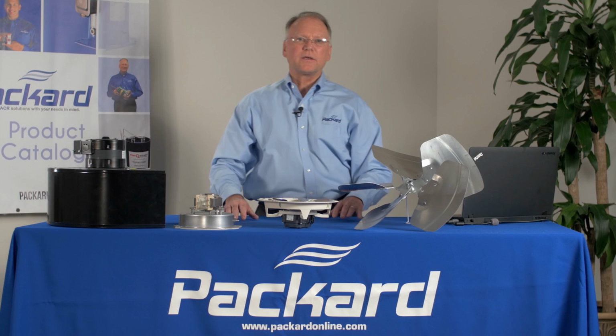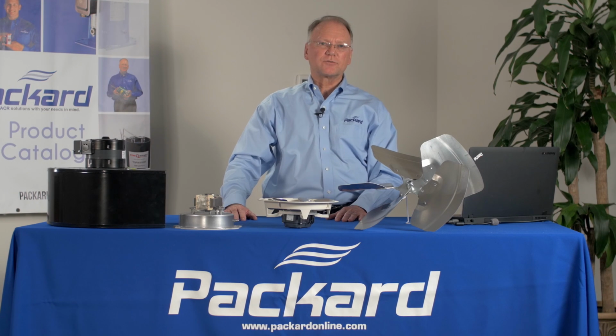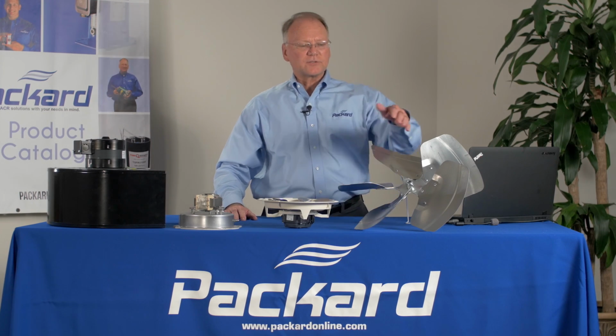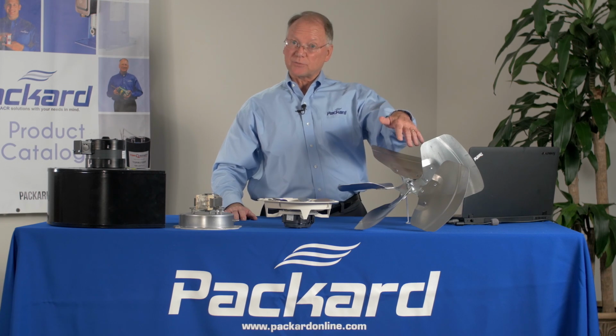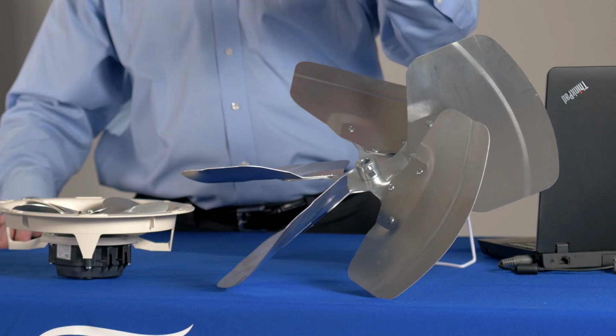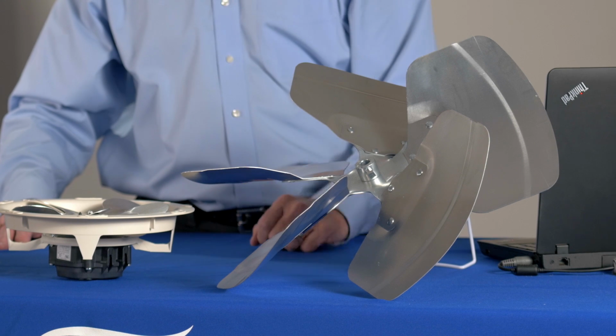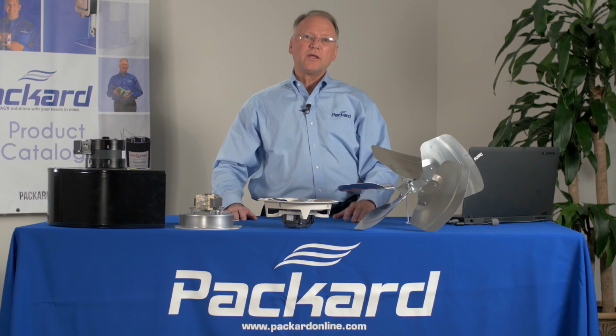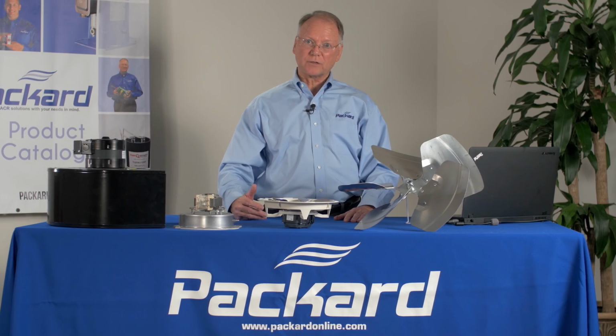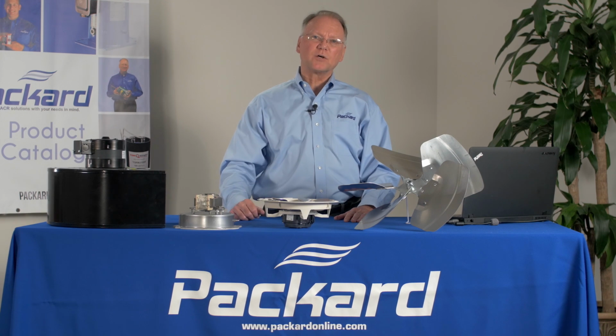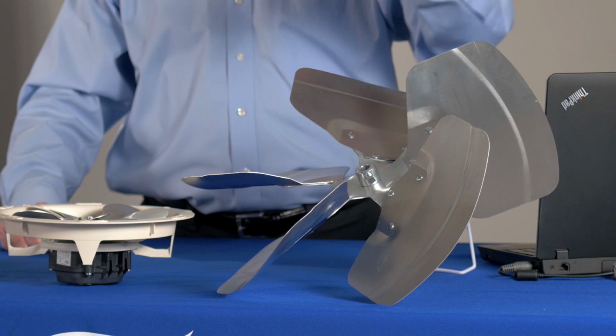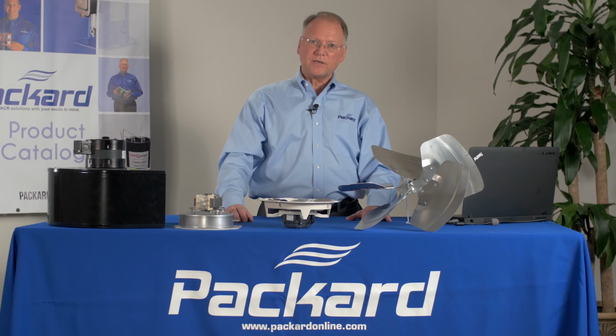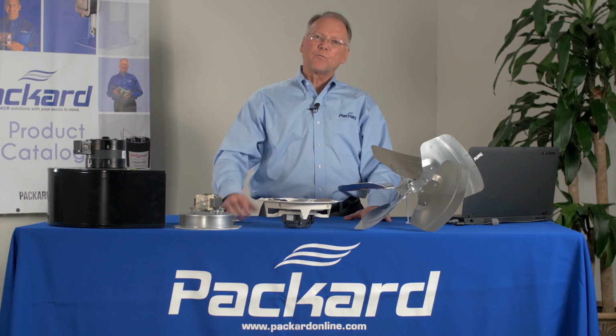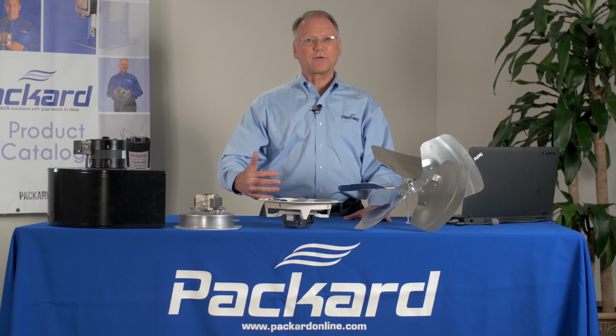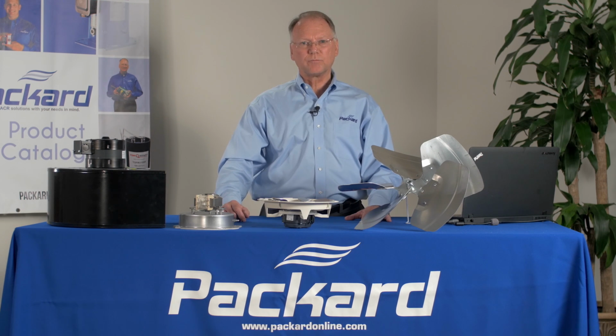We'll move from the evaporator section to the condenser section. With the condenser, instead of a blower, there's not as much static pressure, so we do use a fan blade on the condenser section. The fan helps to remove more efficiently the heat that's been absorbed into the refrigerant. So the fan will blow through the condenser coil, removing heat to the outdoors where it's unobjectionable.